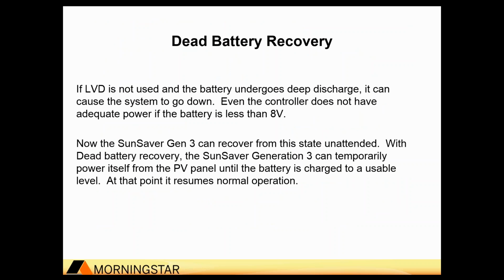And into a couple of the last features that I just want to touch on real quickly that are unique to the Gen 3 and unique to oil and gas and hazardous locations is a dead battery recovery. This feature we've added allows the controller to divert solar current to the battery even when the battery is below the 8-volt threshold to power on the controller. It will essentially let the battery, or attempt to allow the battery, to come back up with the solar resource that's available. It will only work for those cases where the load uptime is not critical. Often, I think these extremely low voltages do initiate a service call of some type. This is intended for those extremely remote places where no one will likely make it to perform maintenance on the system.